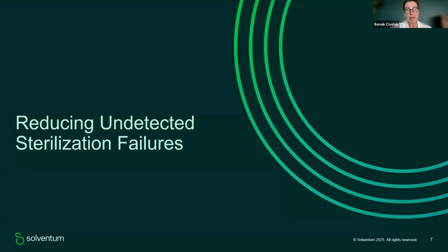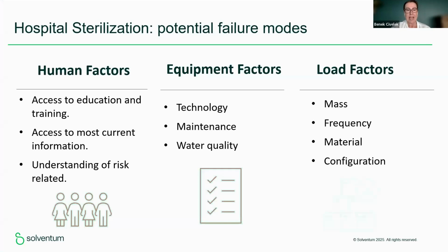Our aim today is to discuss how to reduce undetected sterilization failures. We have the solutions of equipment control, load control, and internal pack control, which can help the CSSDs reduce these failures. When we look at the failure modes, we have already discussed the challenges. So we know about the human factors, because the units are being prepared, cleaned, inspected, and sterilized by the staff. And equipment is an important factor because we have to keep up with the technology, with the sterilizers, and also all the instruments that we're taking care of.